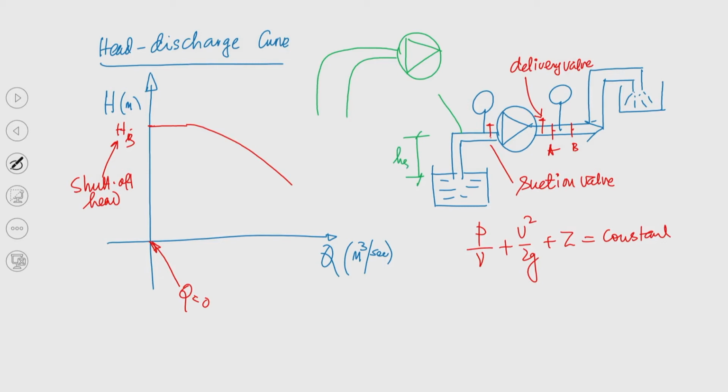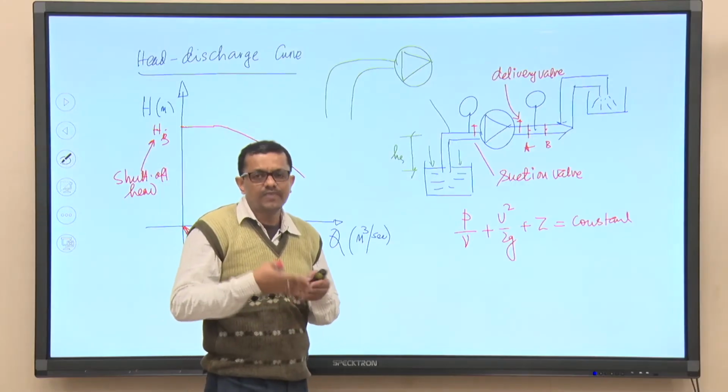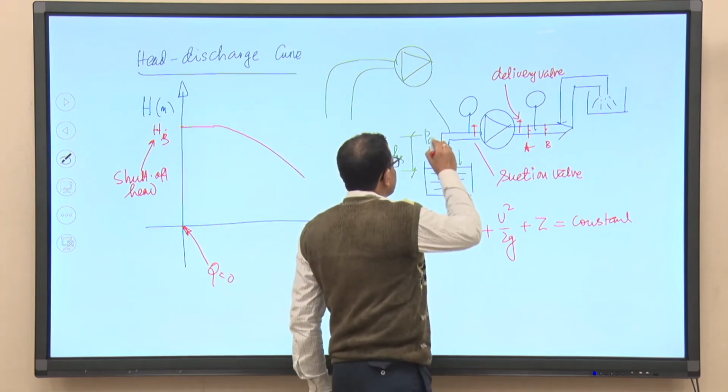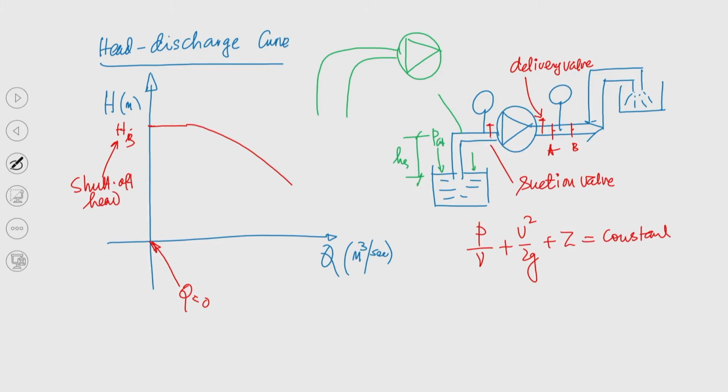Okay. Now, when the pump is started, atmospheric pressure is acting here, and that atmospheric pressure minus the pressure available at the inlet to the pump is the driving force, which is responsible to make the flow occur from this point to the pump inlet. So, basically this is P ATM and here we have P suction. Now, this P ATM minus P suction is the driving pressure to make the flow occur from point 1 to the inlet to the pump, say it is S.